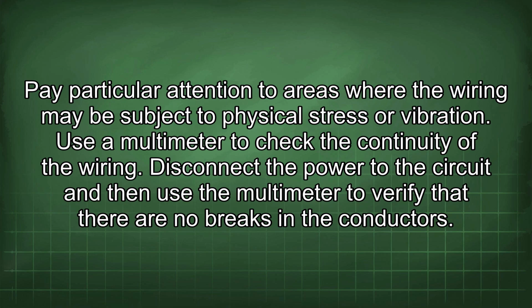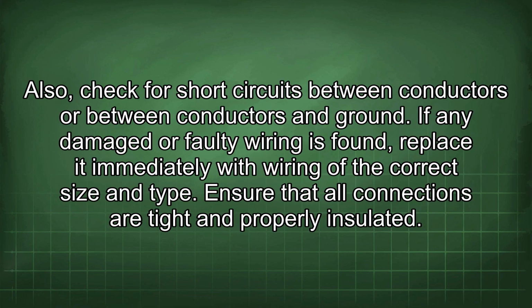Use a multimeter to check the continuity of the wiring. Disconnect the power to the circuit and then use the multimeter to verify that there are no breaks in the conductors. Also, check for short circuits between conductors or between conductors and ground. If any damaged or faulty wiring is found, replace it immediately with wiring of the correct size and type. Ensure that all connections are tight and properly insulated.